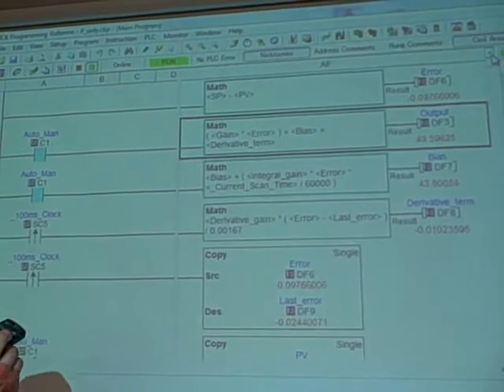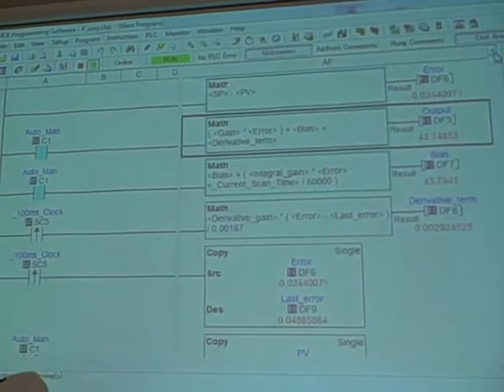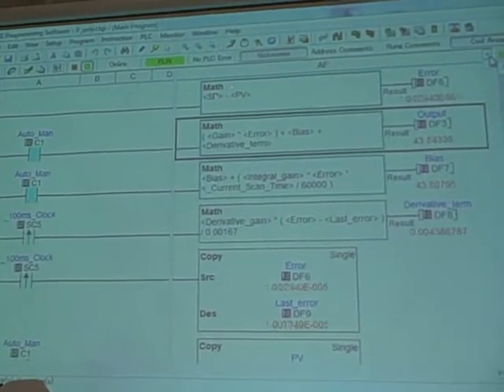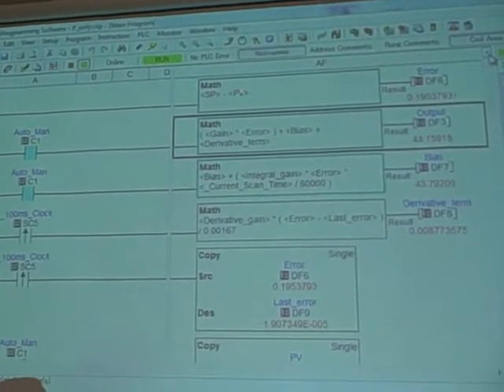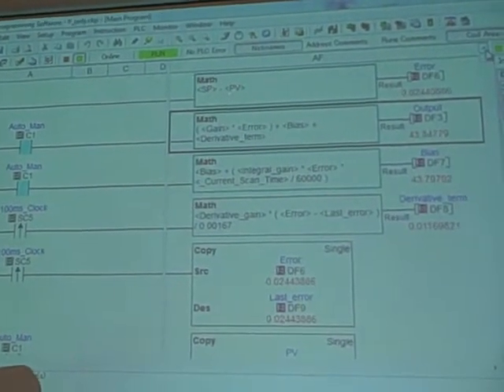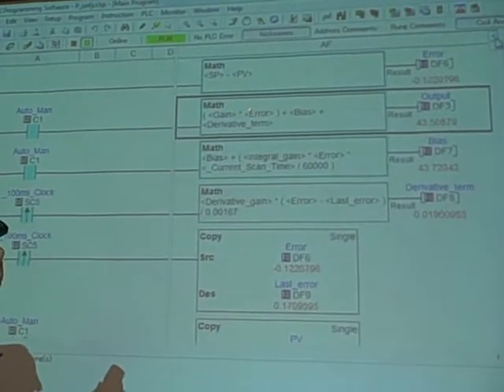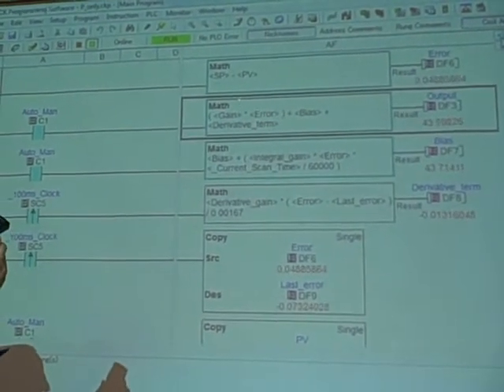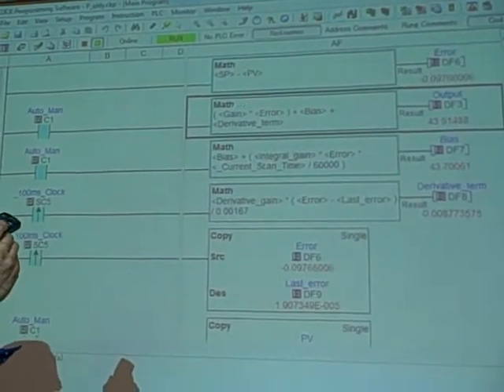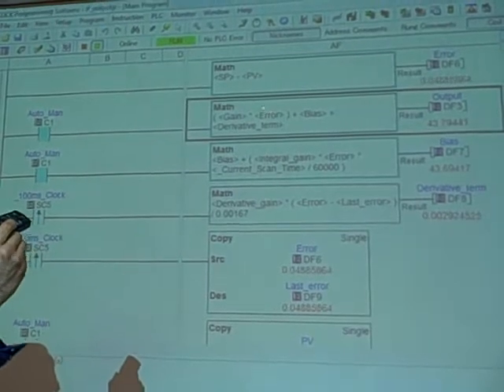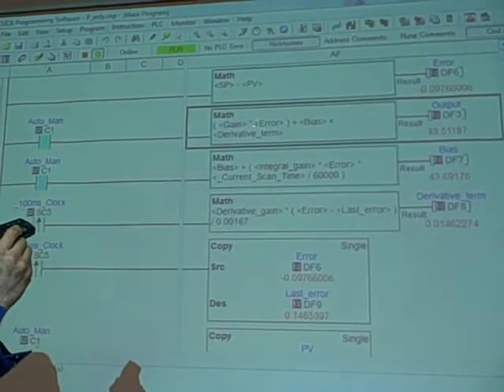Looking through our program, the very first rung we have, we're calculating the error, setpoint minus PV. We're doing it this way because we want reverse action. Here, the next math statement, we're actually multiplying our gain times error, which is a proportional term.